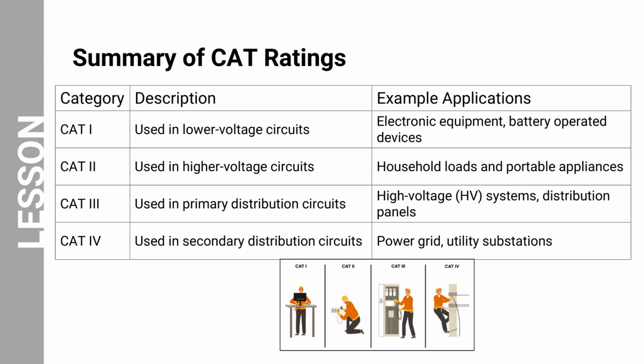Cat 2 rated equipment is designed for local-level electrical systems, such as household and portable appliances. It can be used to test electrical systems in residential and commercial buildings. Cat 3 rated equipment is intended for fixed installations, such as distribution panels and industrial systems, and is also suitable for handling most current BEV high-voltage systems. Cat 4 is intended for use at the source of the installation, such as at power substations and overhead power lines.